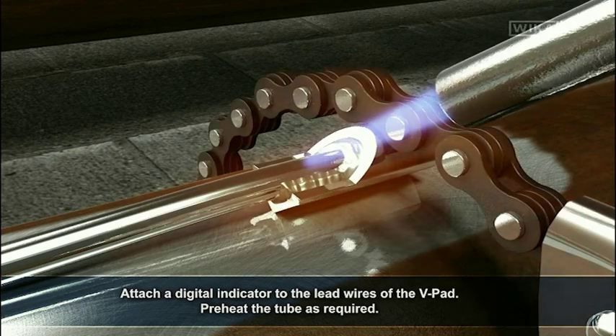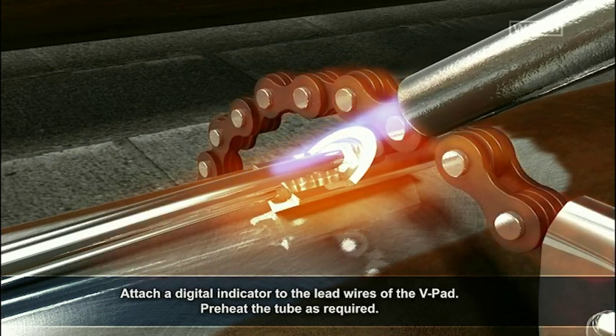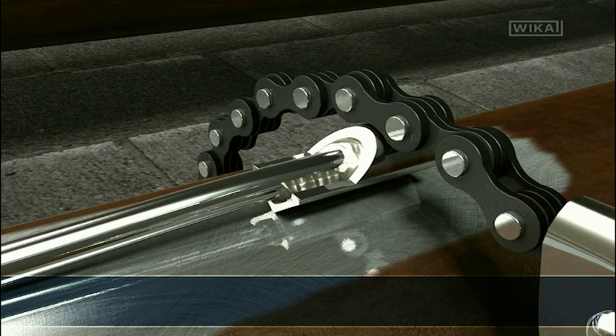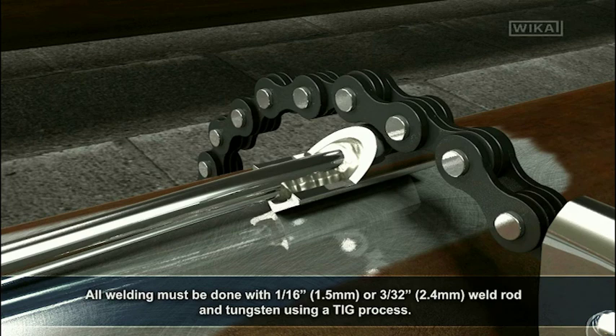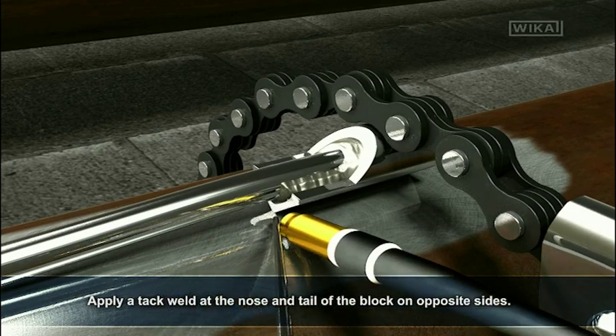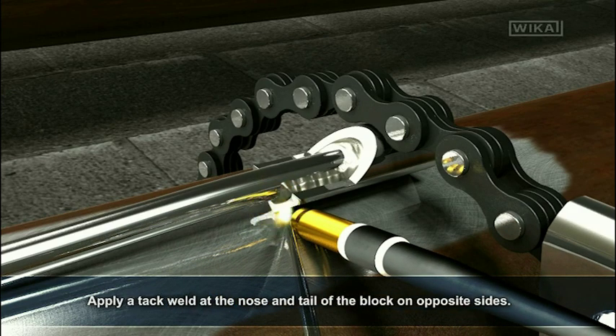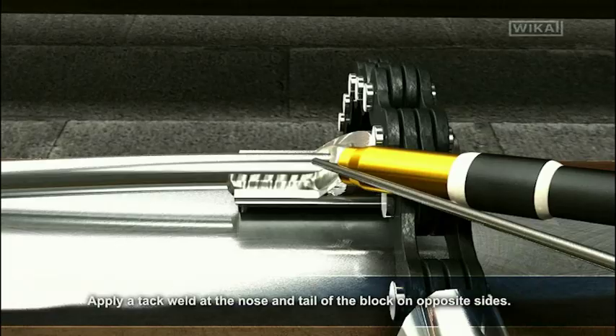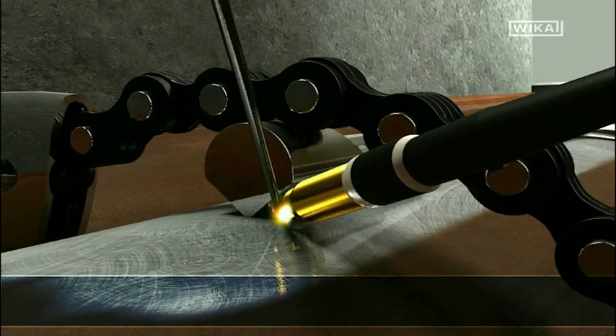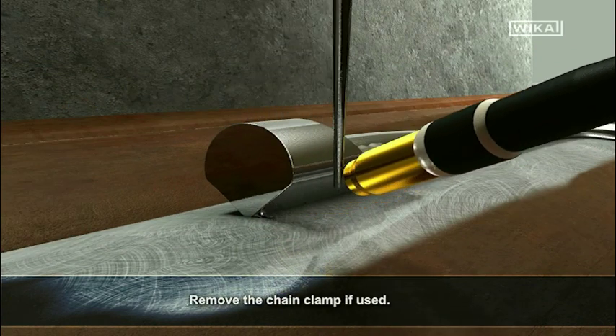Attach a digital indicator to the lead wires of the v-pad. Preheat the tube as required. All welding must be done with 1/16th inch weld rod and tungsten using a TIG process. Apply a tack weld at the nose and tail of the block on opposite sides. Remove the chain clamp if used.